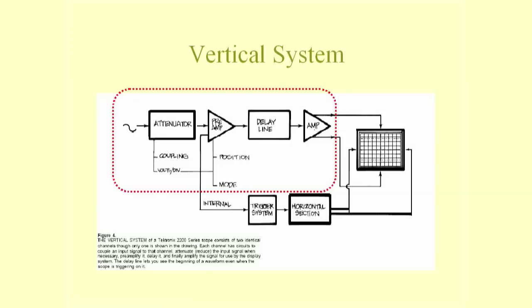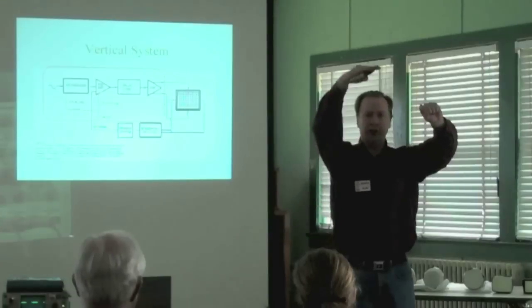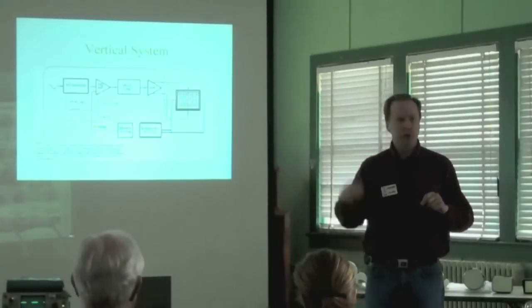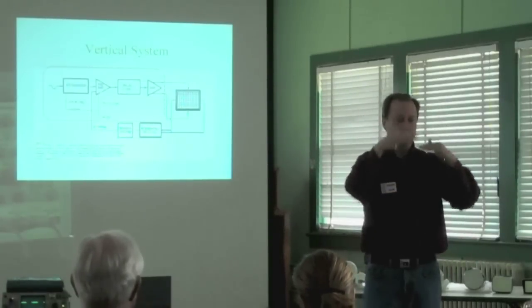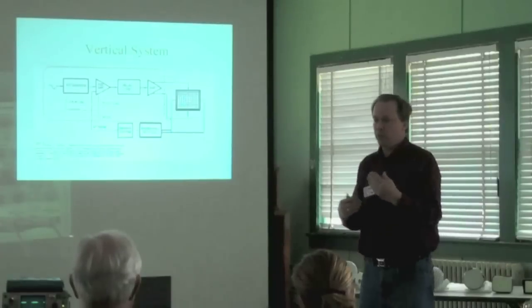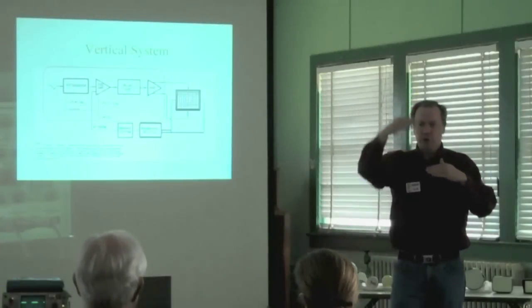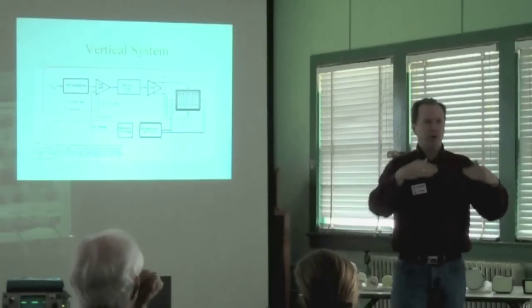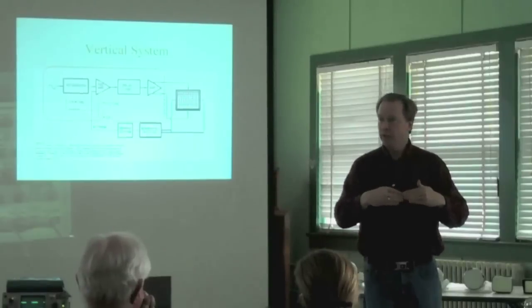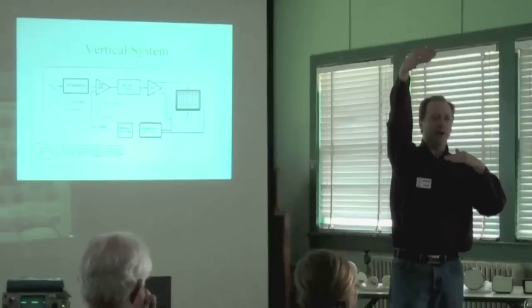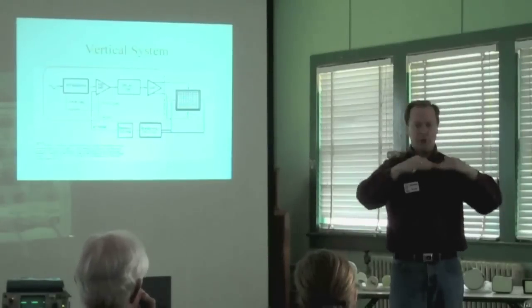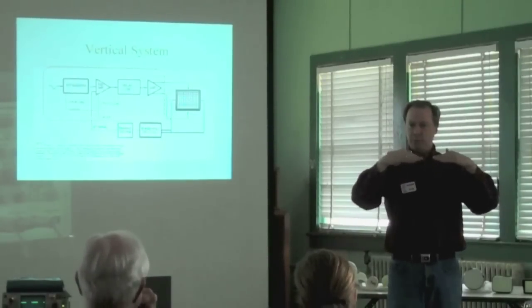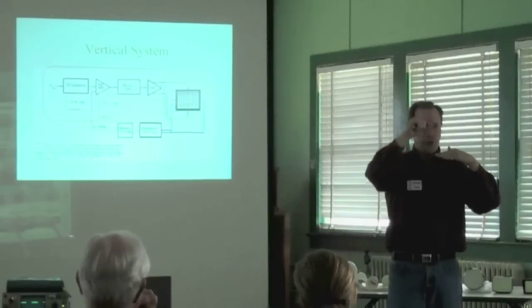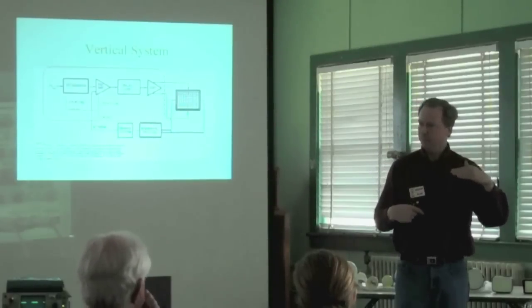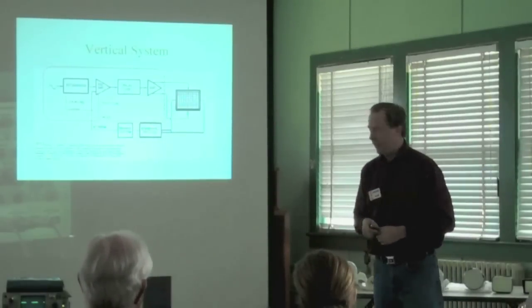You'll also have a position control. That's kind of obvious. You adjust that, it moves the trace up or down. Most of the time you've got the trace centered, but there might be cases where you want to move it somewhere else, because you might want to look at how all my voltages are changing with respect to some power supply voltage, or maybe to ground. If I know everything is at ground or above, I might move the position so that when I touch ground, it's sitting down at the bottom, so I can actually look at the voltages and where they are with respect to ground. So the position helps you do that.